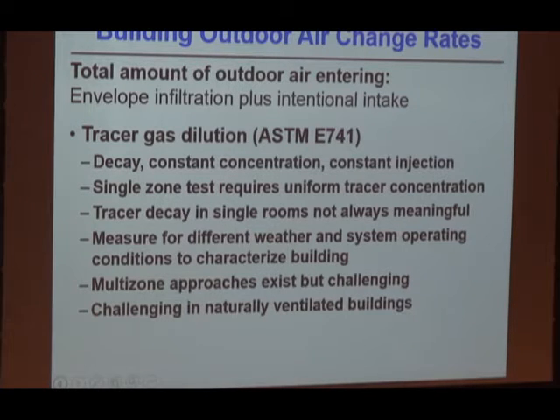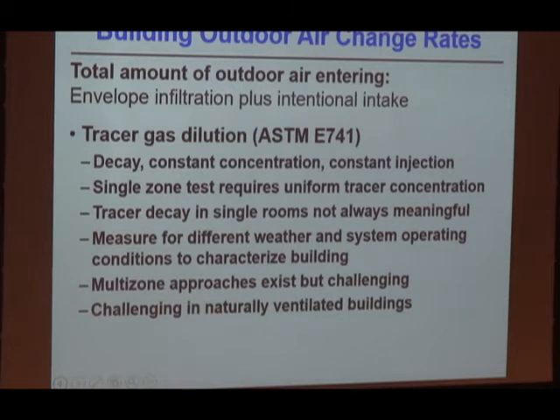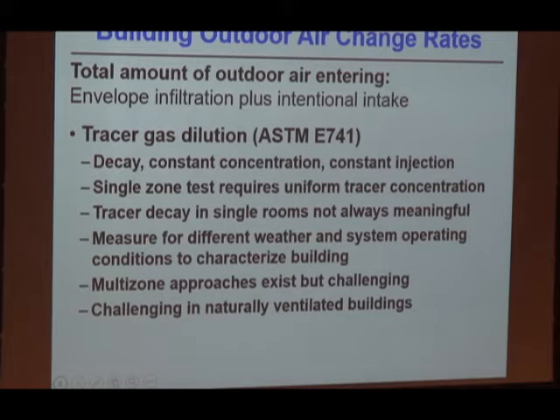Air change rates vary with weather and with system operation. To fully characterize the ventilation characteristics of a building, you need to make multiple measurements under different weather and operating conditions. Multi-zone tracer techniques exist but are really complicated. When you have a naturally ventilated building it can be very difficult to do tracer gas measurements because of the mixing assumption — I'm a little skeptical of some rates reported in naturally ventilated buildings because it is such a challenging measurement.